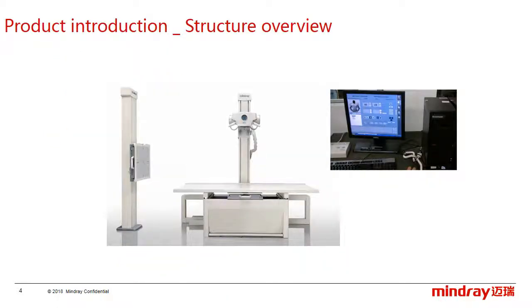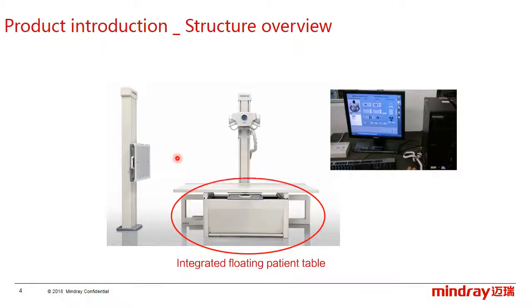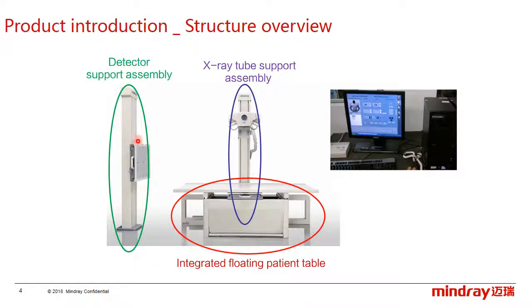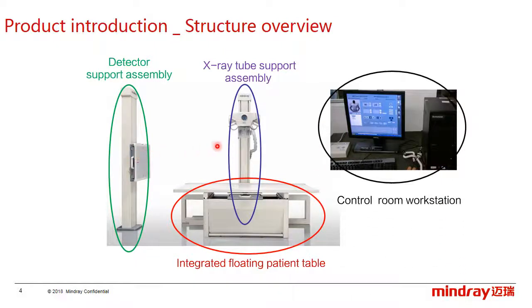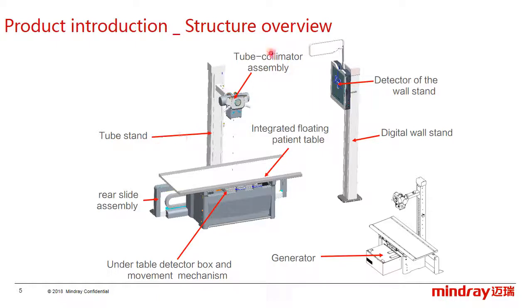Let's see the short overview for this system. This is the integrated floating patient table, the tube stand, and the detector support assembly, or we can call it wall stand. For more detail, this is the tube stand, and the tube collimator assembly is installed on the tube stand, and the tube stand can move on the rear slide assembly. This is the tabletop, and the generator and the under table detector are under the tabletop, and here is the wall stand.